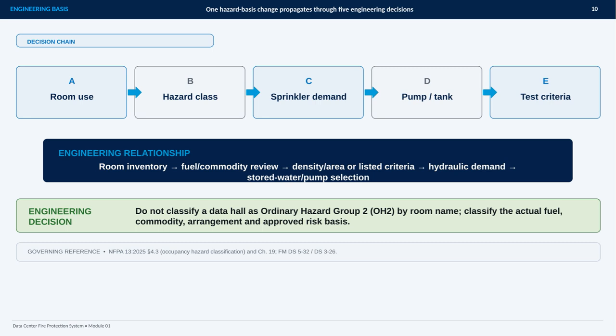From there, the selected criteria determine the required density and area, or an applicable listed design approach. That drives the hydraulic demand, which then informs stored water volume and pump selection. Finally, the test criteria must confirm that the system performs as intended. So, the practical takeaway is simple. One hazard basis change can affect every downstream engineering decision. The governing references shown here are NFPA 13, including occupancy classification and the relevant design chapter, along with FM guidance documents DS 5-32 and DS 3-26.